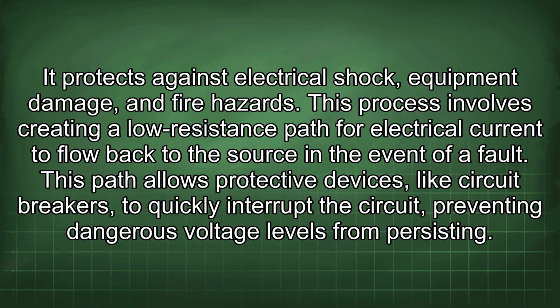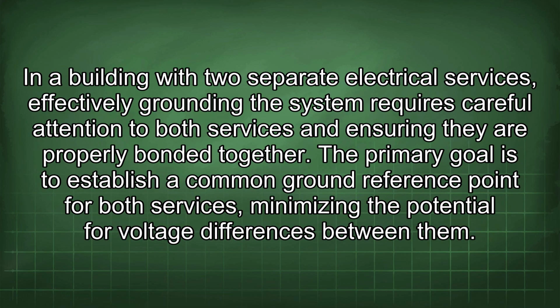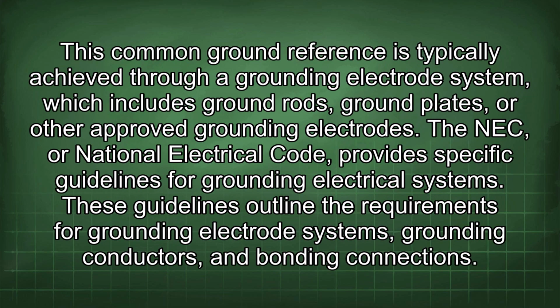In a building with two separate electrical services, effectively grounding the system requires careful attention to both services and ensuring they are properly bonded together. The primary goal is to establish a common ground reference point for both services, minimizing the potential for voltage differences between them. This common ground reference is typically achieved through a grounding electrode system, which includes ground rods, ground plates, or other approved grounding electrodes.